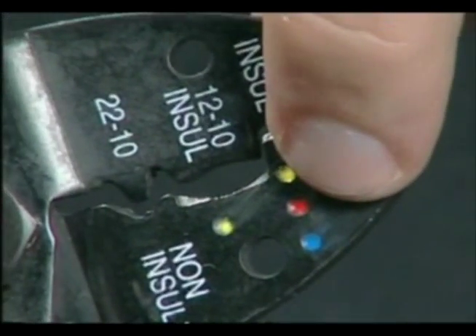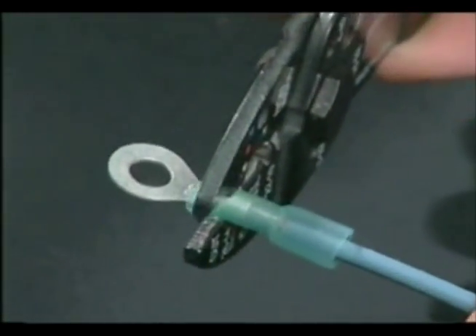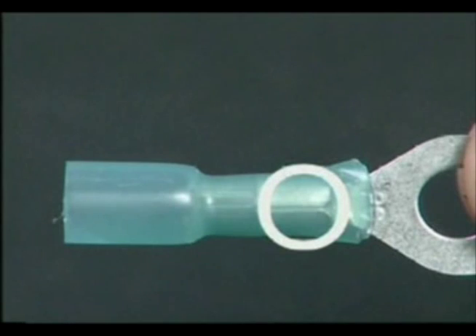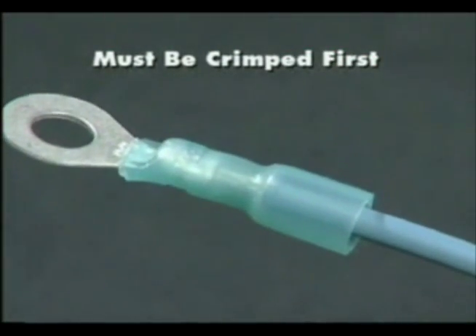Use the proper crimp die and crimp the terminal. Be sure to crimp the terminal barrel and not the solder sleeve. The terminal must be crimped before heating and soldering.